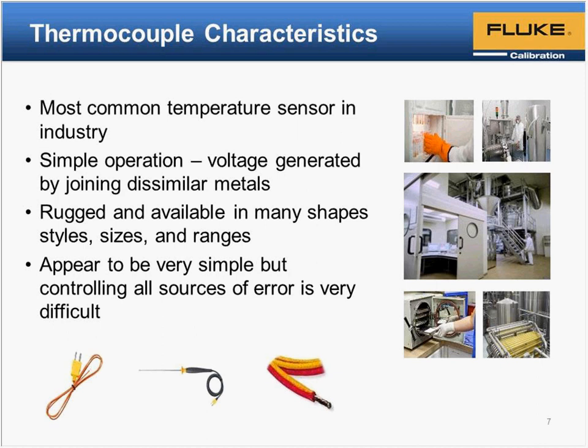First of all, the thermocouple is probably the most common temperature sensor in industry, and they are used everywhere. The reason is that they're very simple to build and can measure temperature. At a basic level, they are a temperature sensor based on a voltage. It occurs by connecting two different metals together, and the electrical characteristics of connecting these two metals change with temperature. So as temperature goes up, the voltage will go up. They are also very rugged because the sensor is basically just wire.